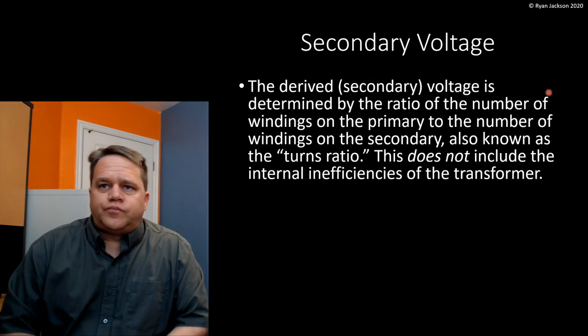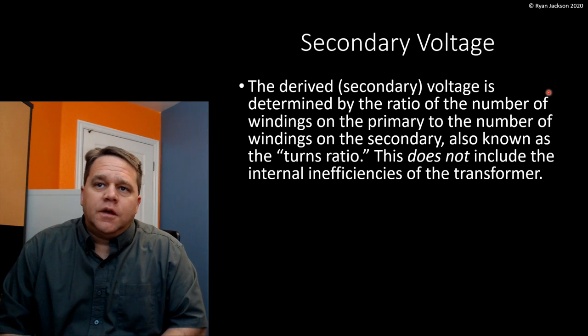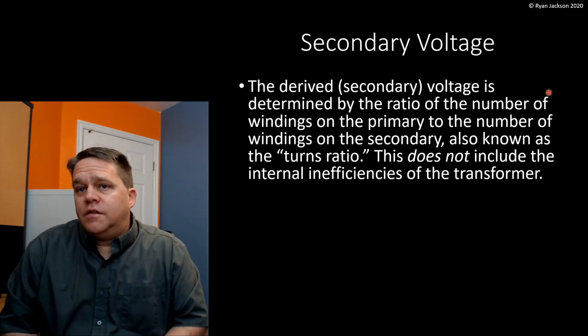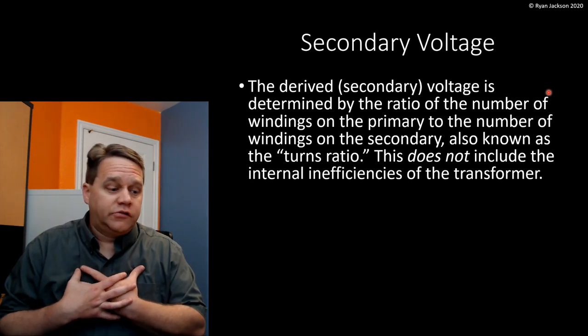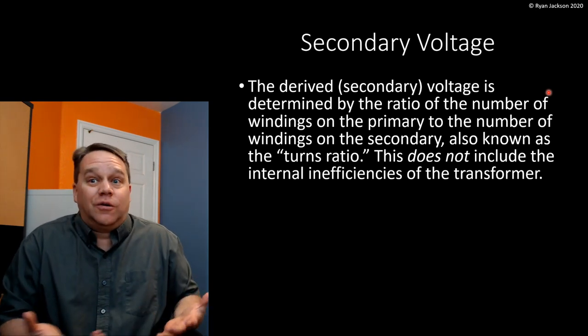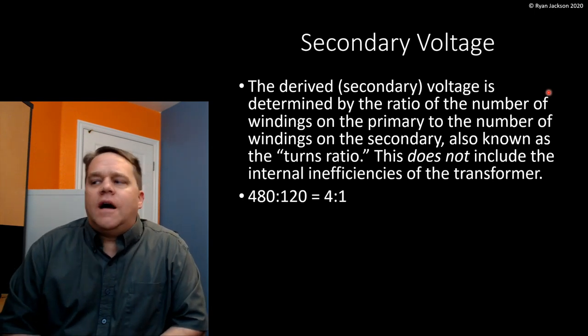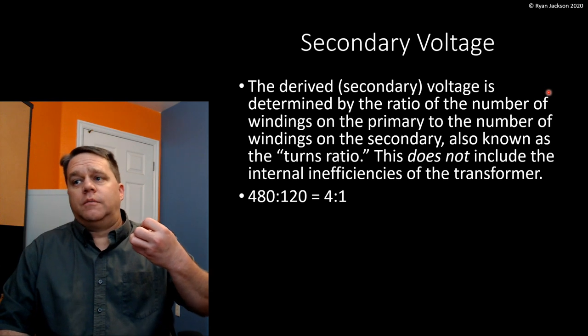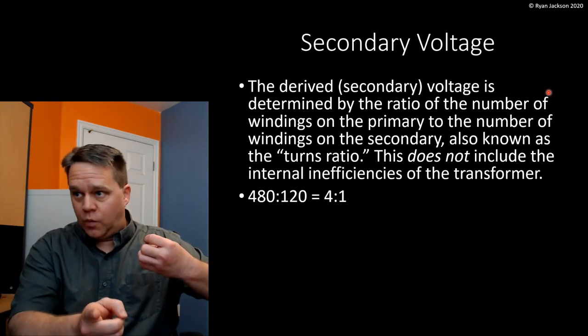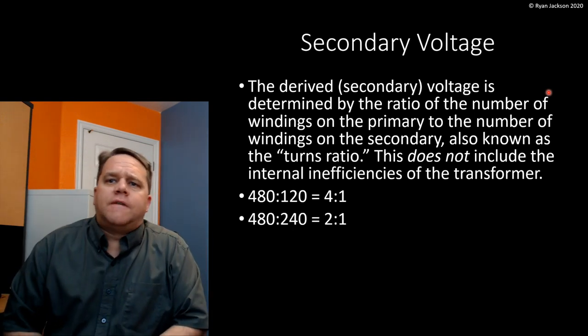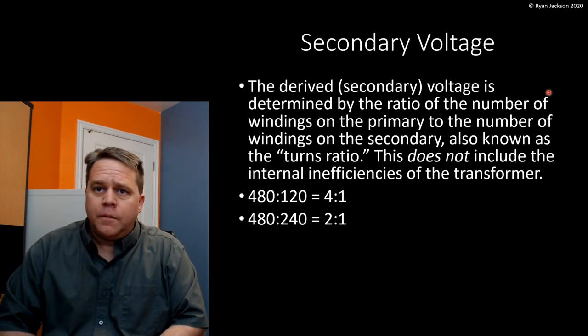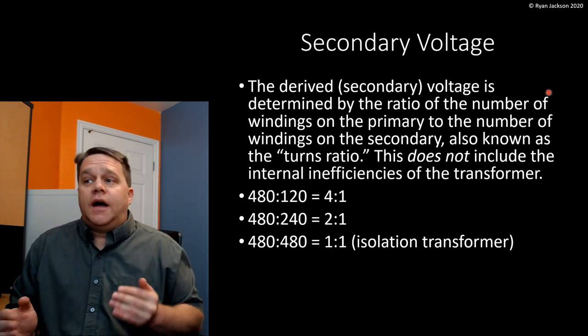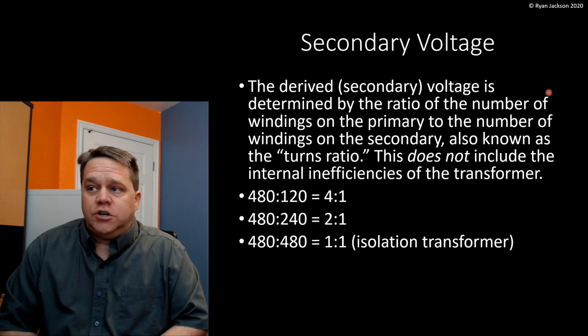The derived secondary voltage is determined by the ratio of the number of windings on the primary to the number of windings on the secondary — also known as the turns ratio. This does not include internal inefficiencies of the transformer. If I have a primary of 480 and a secondary of 120, the turns ratio is 4 to 1. From 480 to 240 would be a 2 to 1 ratio. From 240 to 120 is also 2 to 1. And if I want to go from 480 to 480 — a 1 to 1 ratio — we call that an isolation transformer. We create a new system without wanting a new voltage.